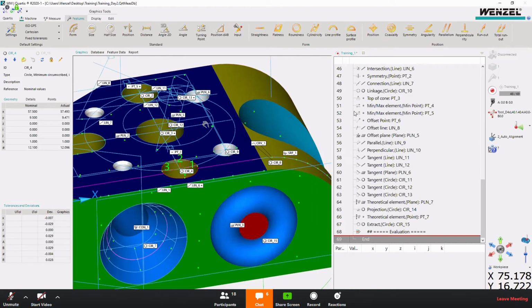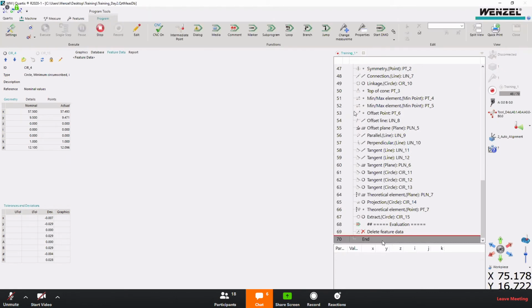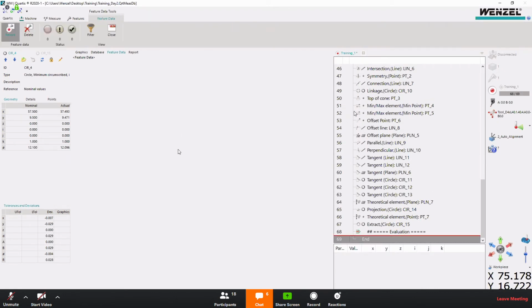I start for the evaluations, we have these things called features data. So this is the feature data. Meaning that if later I make any evaluations of the features and then I record the features data, I activate this recording. This record is different from the programs. And then if I activate this, the features like maybe the diameter, the radius that I output will show live here. It will show you live here, but it is not in the report yet. It's only shown in the software.